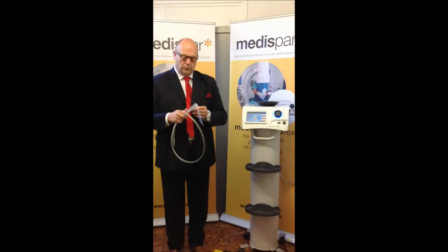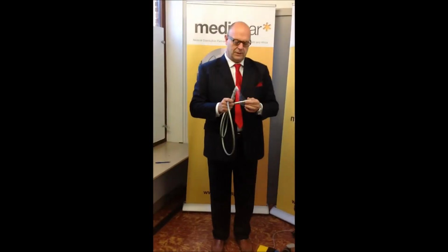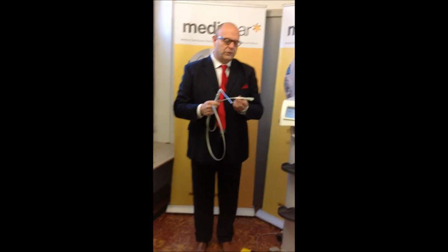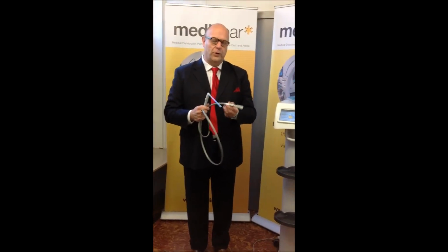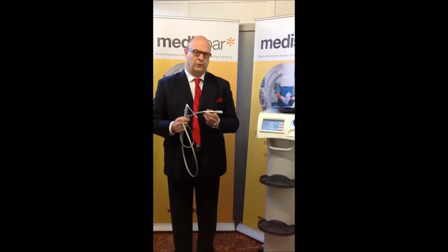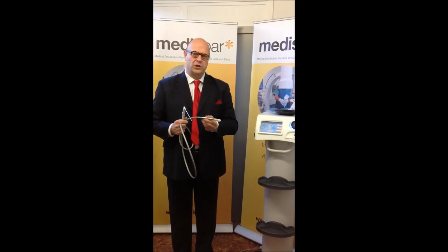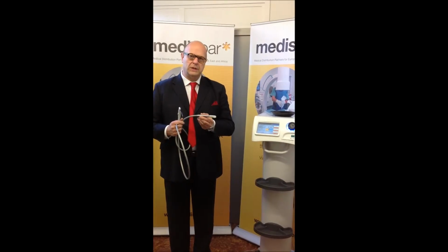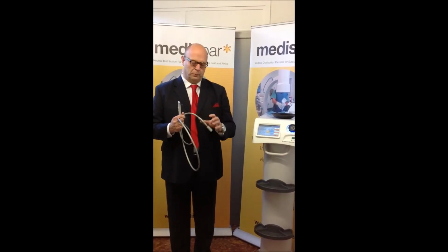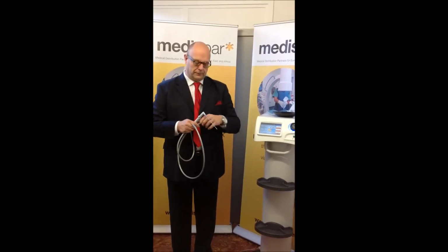Also, the probe is steam sterilized, and at the end you will see a protective cap. It's very important to use this protective cap during your sterilization process, because otherwise it might damage your whole probe and you need to discard it.